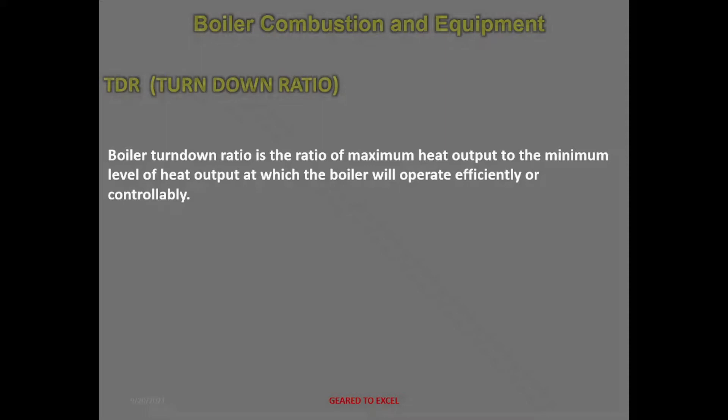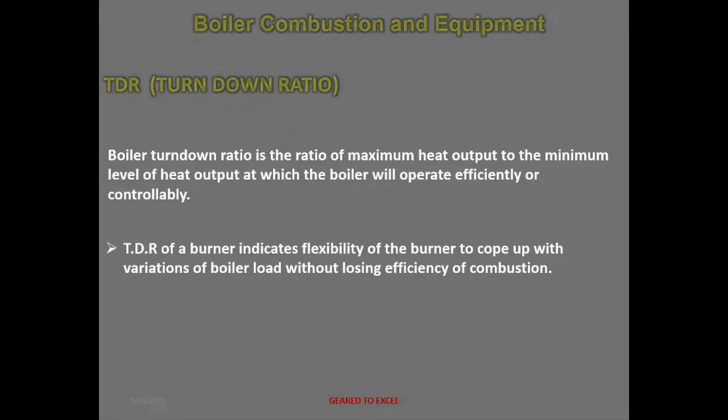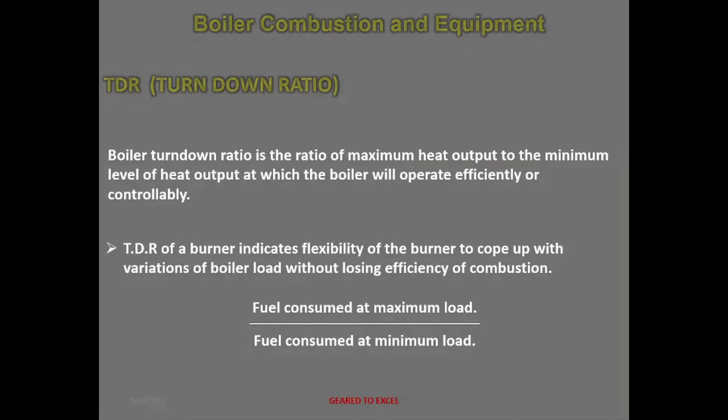TDR — Turndown Ratio. Boiler Turndown Ratio is the ratio of maximum heat output to the minimum level of heat output at which the boiler will operate efficiently or controllably. TDR of a burner indicates flexibility of the burner to cope with variation of boiler loads without losing combustion efficiency. TDR is fuel consumed at maximum load to fuel consumed at minimum load.